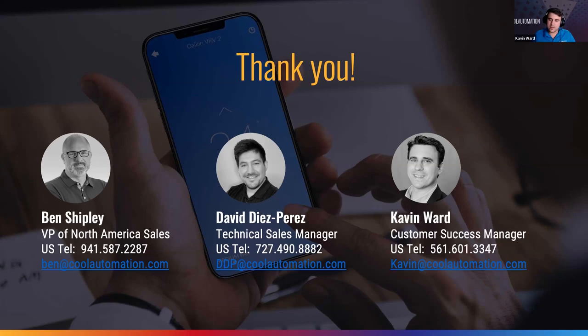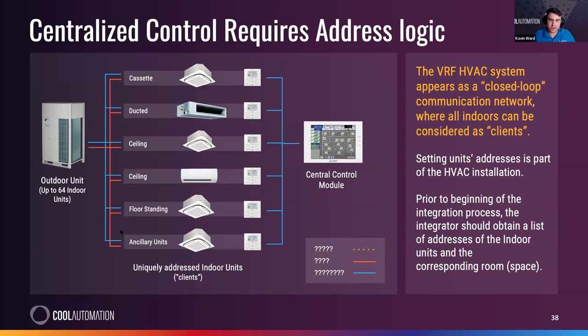One of the most common troubleshooting requests I receive when tying into a VRF system is that it doesn't auto discover. On the VRF side, when the system is commissioned properly for central control, it truly is plug and play—you land your two wire connection from Daikin, Mitsubishi, Toshiba, LG, etc., and the units automatically load on the touchscreen immediately. When that doesn't happen, it's typically because there's an addressing issue or a step that was skipped during installation, where the indoor units don't have a central control address assigned, or some other commissioning piece isn't activated on that VRF system.